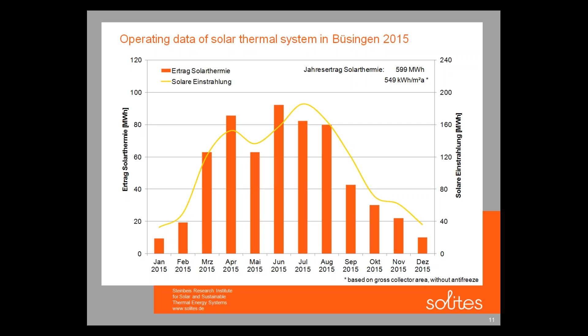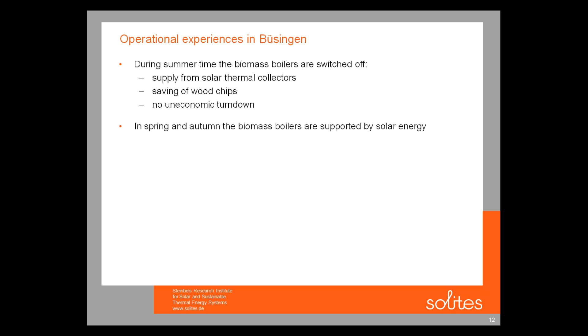To understand a little better how the system works, you see some operational issues on the next slide. During summertime the biomass boilers are switched off completely, so the supply comes from the solar thermal collectors, which saves wood chips and avoids uneconomic turndowns of the boilers. In spring and autumn the biomass boilers are running and are still supported a little by the solar collector field, and during the heating season the solar share is quite low. Looking at the solar fraction in heat generation, in summertime we have 100%, and looking at the whole year, the solar fraction in heat generation is about 13%.